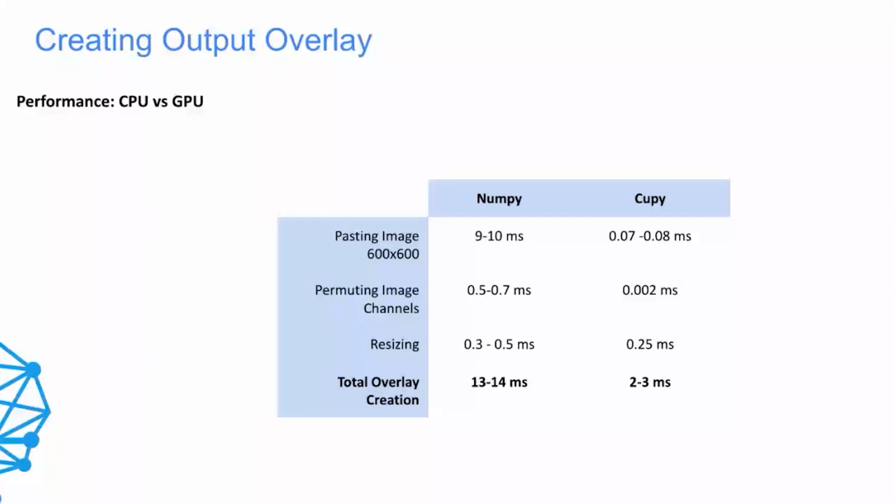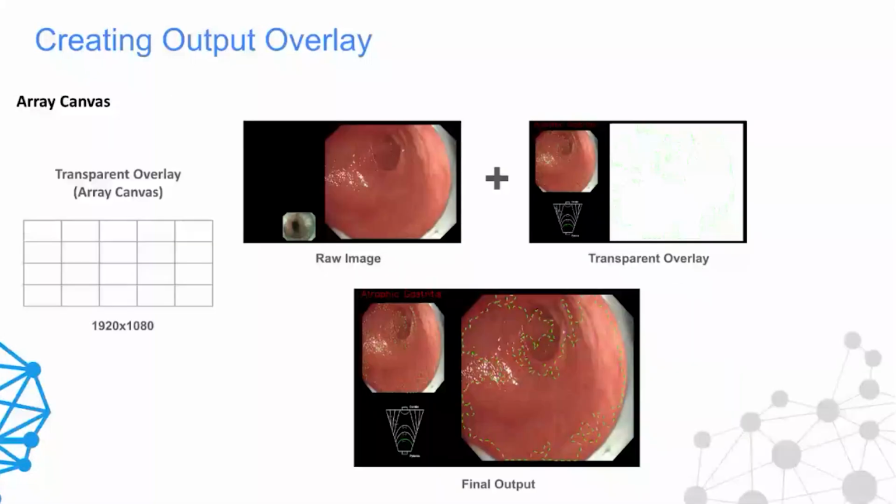It is very critical because over here, all the left-hand side content can still be near real time, but anything you are showing on the live image has to be exactly real time, less than 50 milliseconds. In fact, quite a lot less than 50 milliseconds, so that the display time can be enhanced as well.